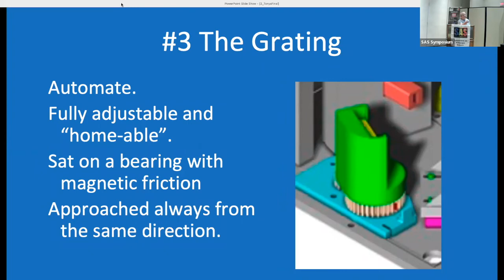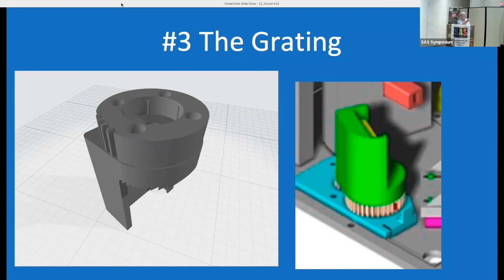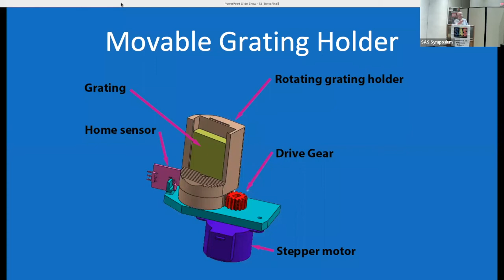We do the actual wavelength selection. We always approach it from the same direction, so you take up the slack in the gears. It is repeatable. You can slew this thing a couple of thousand angstroms if you want, and it will go back to the same place within a couple of pixels. Job done. There's the grating holder. That's the detail. We built in a home sensor to provide a homing mechanism. So if you get lost, you can press the home and it will go back to a reset position.